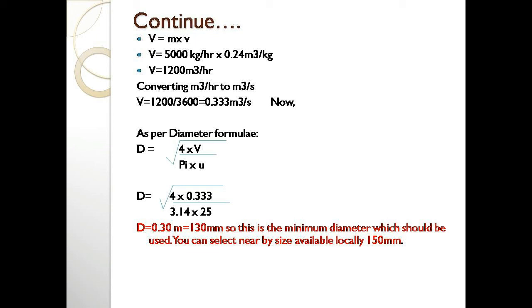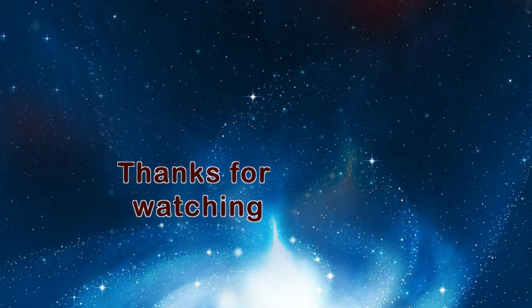Since 130 mm is not a standard available pipe size in the market, we select the nearest upward standard size, which is 150 mm. So a pipe of 6 inches (150 mm) diameter is suitable for a flow of 5000 kg per hour. You can apply this calculation method for any steam flow requirement in your own field.